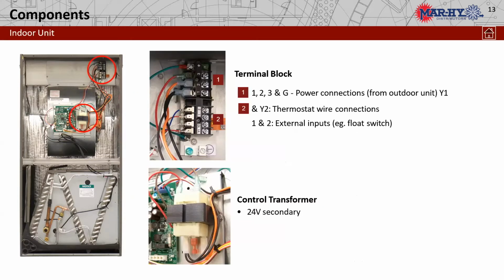So as we look at the indoor unit, we have 2 sets of terminal blocks, one for line voltage, one for the low voltage inputs. Number 1, that's our line voltage, 1, 2, 3, and ground. That probably looks fairly familiar to you, because we are looking at a basic mini split connection as we would have with our mini splits. 1 and 2 being line voltage, 3 being data exchange, and then our ground. So our same wires that we would use for a mini split between the indoor and outdoor is what we're going to use on this application. So there again, our power for the indoor unit comes from the outdoor unit, just like our minis.